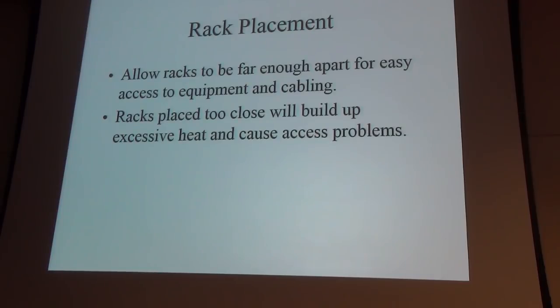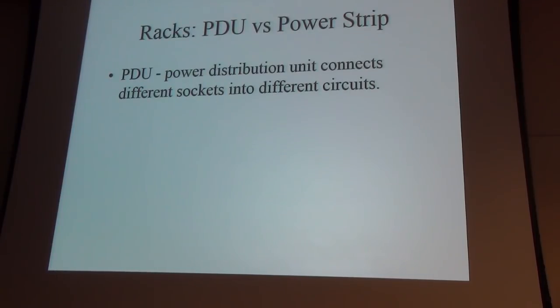Placement is a detailed thing — try to standardize two tile spaces per rack, and leave room in front and back to walk and open rack doors. PDUs: there's a difference between a power strip and a PDU. I've seen many expensive government sites with little extension cords hanging from the ceiling running into servers. PDUs are actually better — nowadays they're intelligent, come with an IP address, and you can inquire how much electricity they're using, shut them off, and plot usage over time.